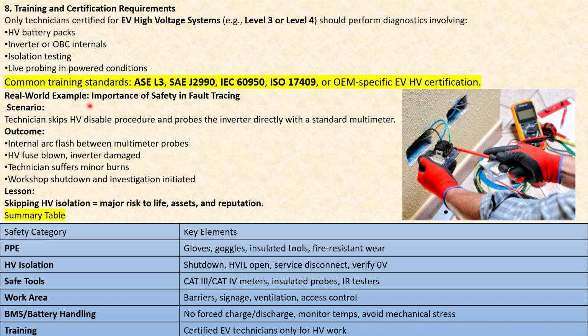Now, talking about a real world example, the importance of safety in fault tracing. The scenario: a technician skips the high voltage disable procedure and probes the inverter directly with a standard multimeter. Talking about the outcome: internal arc flash between the multimeter probes, HV fuse blown, inverter damaged, technician suffers minor burns, and workshop shutdown and investigation initiated. Usually these are the outcomes, the usual mistakes or errors that are observed when safety is not implemented in fault tracing.